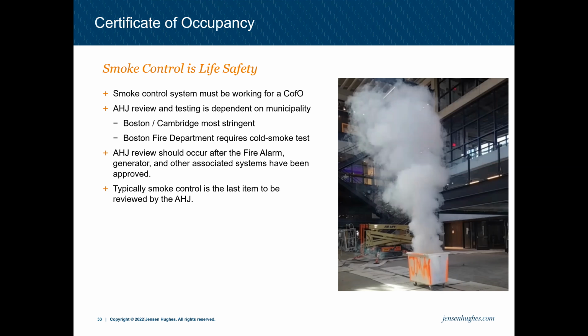AHJ does review, and they should be testing the systems for their own review. Again, Boston and Cambridge are the most stringent. With the AHJ review and acceptance test, Boston does require a cold smoke test. That test is required to show the movement of smoke, and it's typically only required for a smoke exhaust system, so an atrium or a stage traditionally.